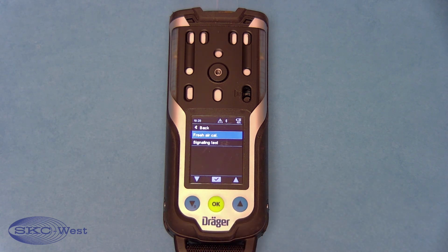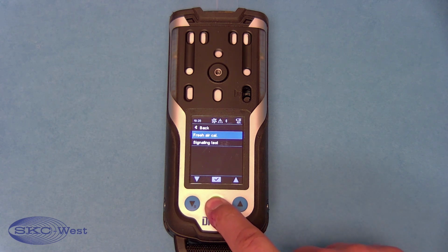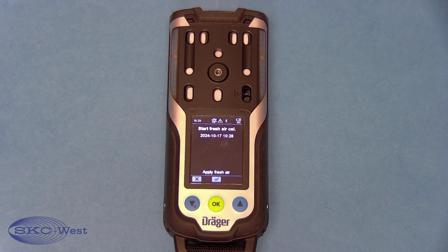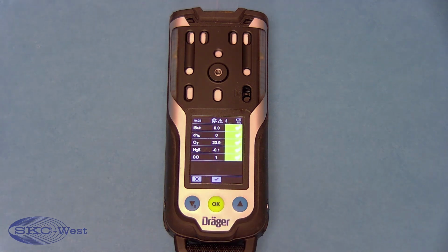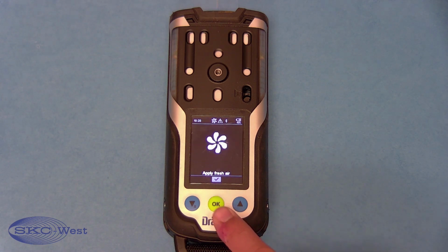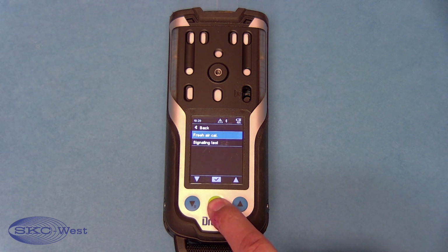Fresh air cal should be highlighted. Push the green OK button one more time to receive a prompt to apply fresh air. Hit the green OK button one more time to go through the process. Once you have all check marks in green boxes to the right of the sensor name, push the green OK button one final time to gain access to the back option on the menu. Highlight back and push the green button to get back to the home screen.